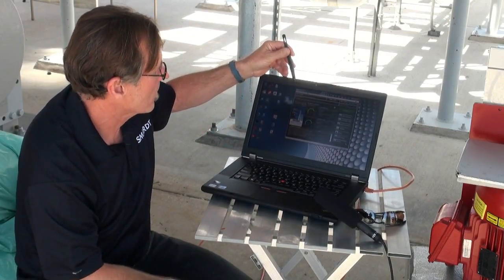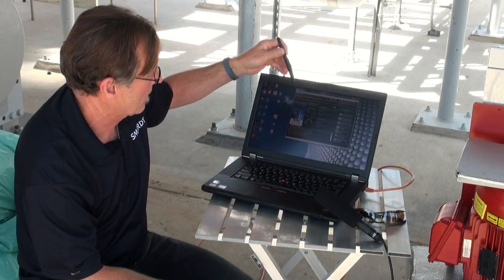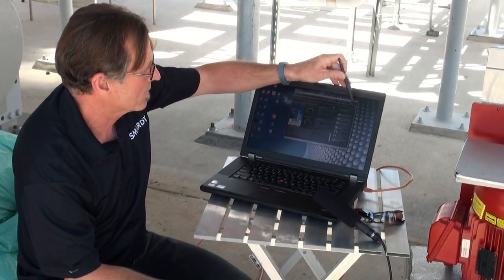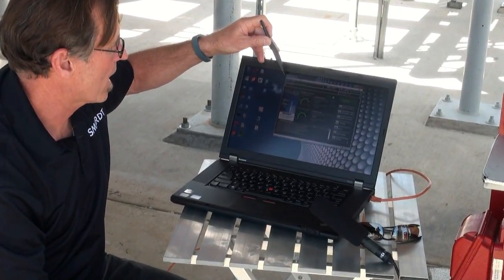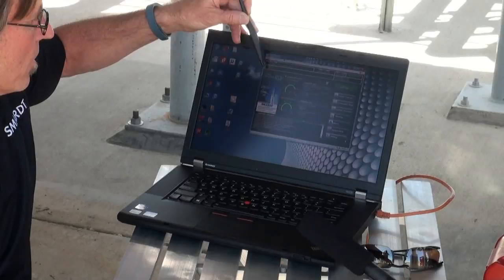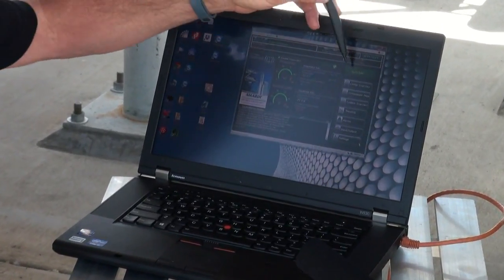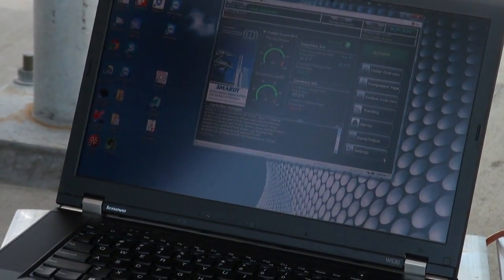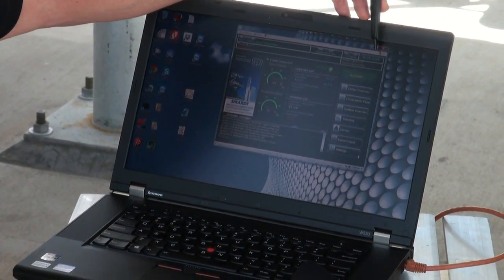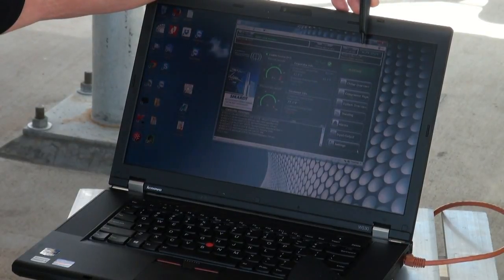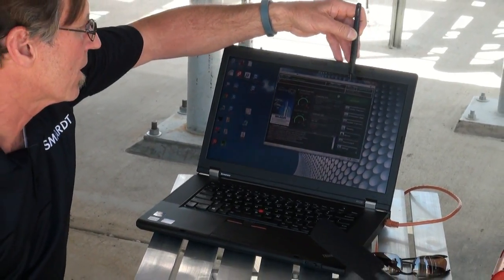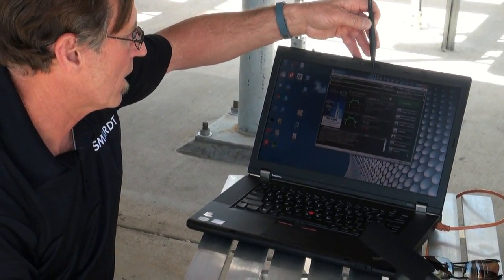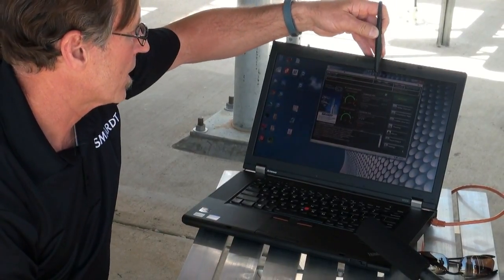The nice thing about this is that every window we look at will have a little box on the top here. It's our status, and on every screen that we go into we'll always have this information. So we have the status of the chiller right now. The state is running normal. Got the date and time. We've got entering water and leaving chilled water. Right now it's pretty close to set point: 46.5 coming in and 42.6 leaving. I think our set point is 42.